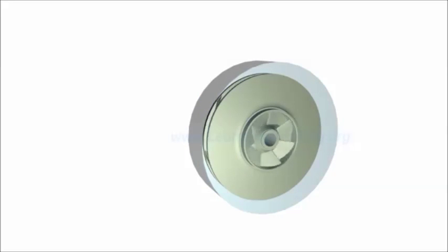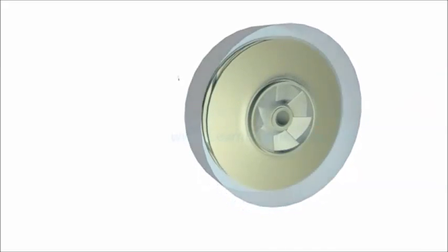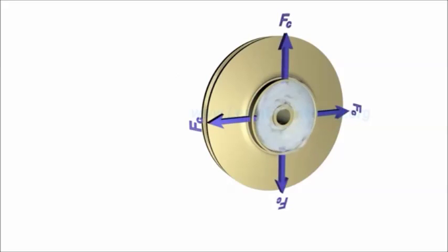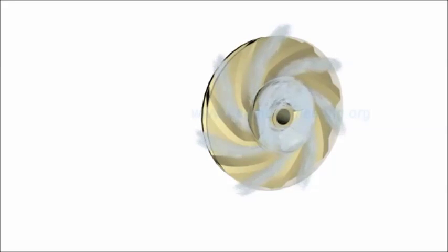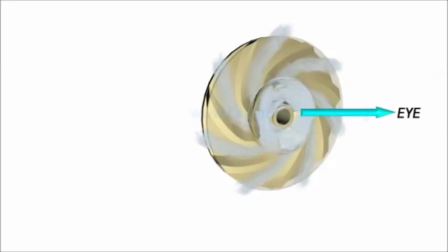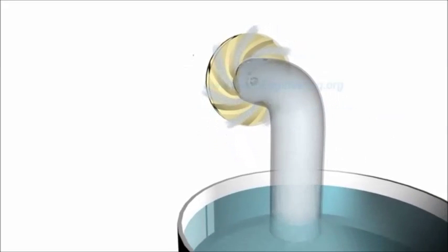When the impeller is made to rotate, it makes the fluid surrounding it also rotate. This imparts centrifugal force to water particles, and the water moves radially out. Since rotational mechanical energy is transferred to the fluid, at the discharge side of the impeller, both pressure and kinetic energy of water will rise. At the suction side, water is getting displaced, so a negative pressure will be induced at the eye. Such low pressure helps in sucking a fresh water stream into the system again, and this process continues.